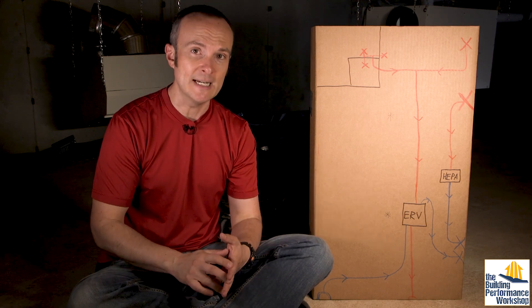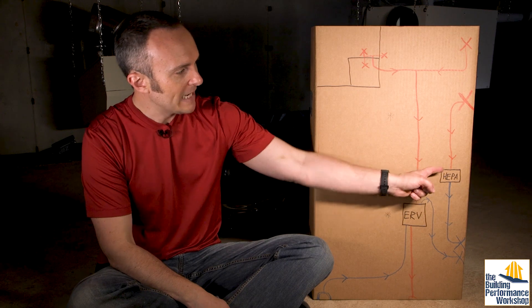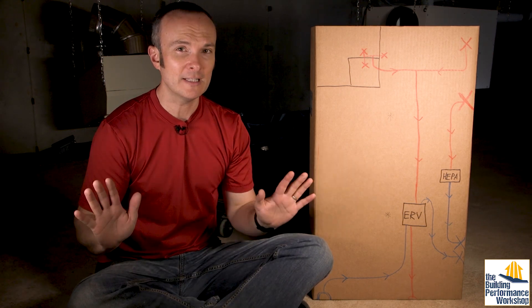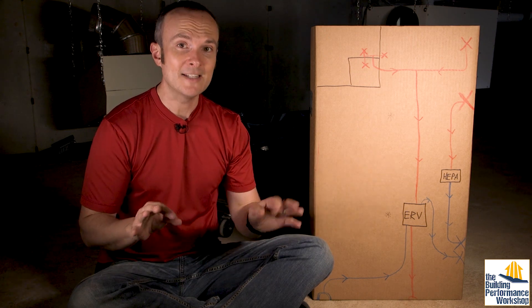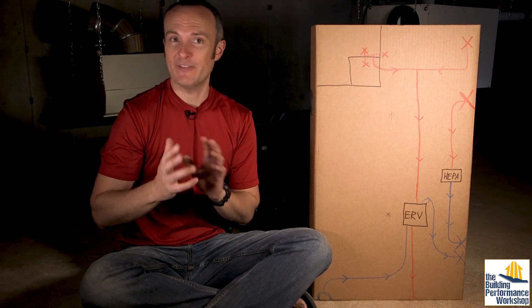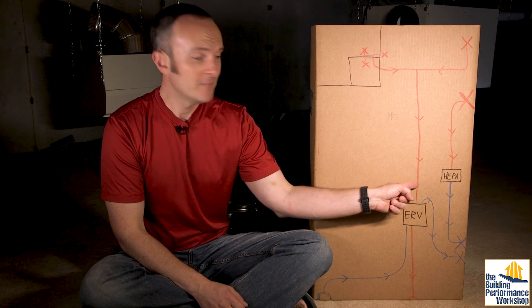To understand this better, here is a diagram. This is the bathroom in the studio space above us — 24 feet wide, 36 feet long, bird's eye view from above. Here is the ERV on my left and the HEPA filtration unit over here. These each have a dedicated duct system. The amount of air contained within this crawl space and the studio above is 15,000 cubic feet. Running the ERV at 150 CFM for one hour changes out 9,000 cubic feet, so it takes less than two hours to change out all of the air — probably more than enough.